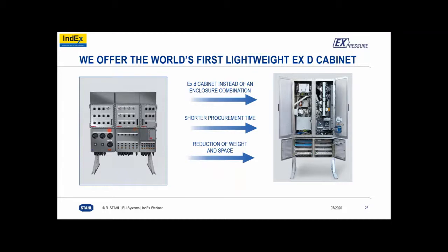So when we look at the cabinet on the left, we're talking about 4 different EXD enclosures and then multiple EXE. Yeah. So if I was an installer, this installation is much more difficult. If we're talking about design, the design is much more difficult. And if we're talking about inspections, well, even more enclosures to open, possibly causing damage. It is a much more cumbersome, time-consuming installation. While with the one over here, it's one EXD enclosure, and perhaps an EB enclosure on the bottom.